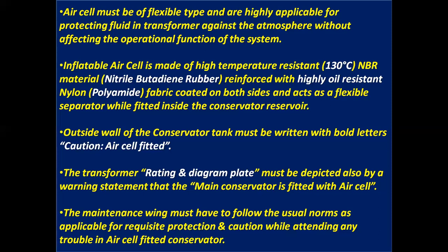Outside wall of the conservator tank must be written with bold letters, caution, air cell fitted. The transformer rating and diagram plate must be depicted also by a warning statement that the main conservator is fitted with air cell. The maintenance wing must have to follow the visual as well as usual norms as applicable for requisite protection and caution while attending any trouble in air cell fitted conservator.